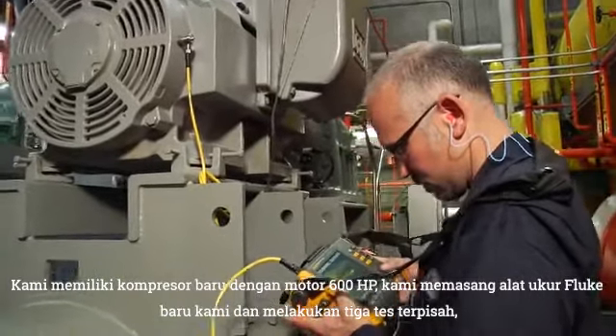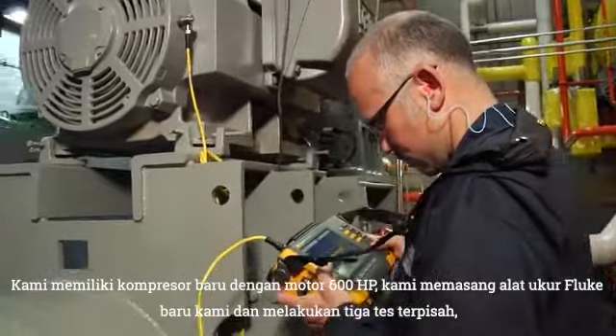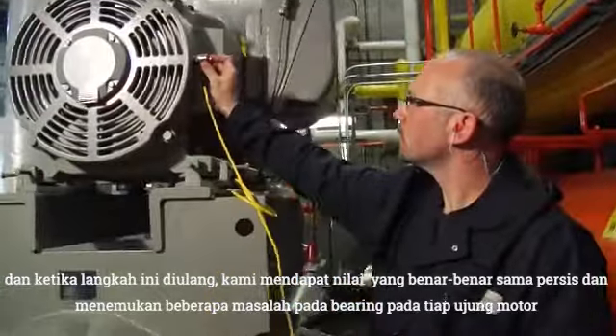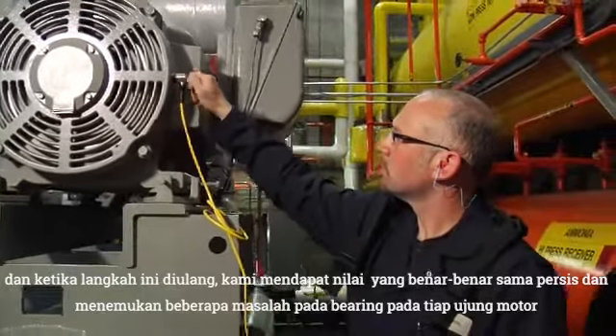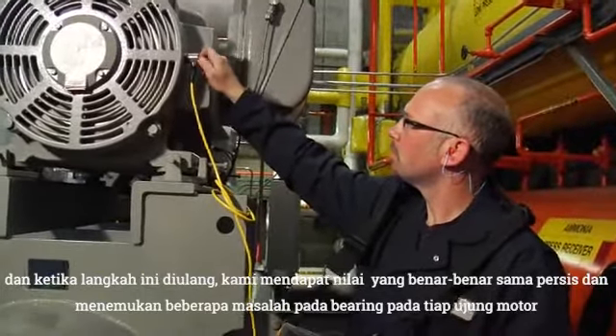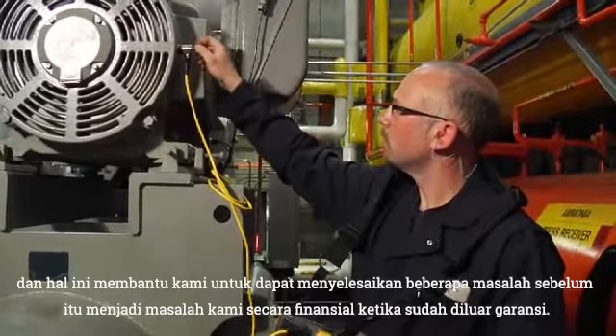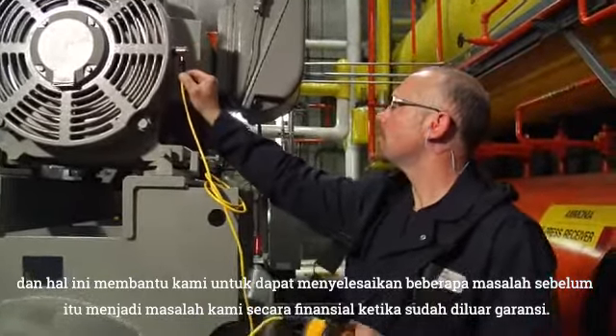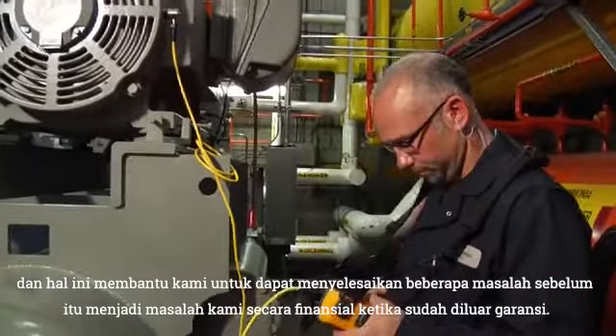We hooked up our new Fluke meter and did three separate tests, and they all repeated exactly the same, and did actually find some slight motor bearing end wear on each end. That's actually helping us so we can get some of these problems taken care of before things like that become out of warranty and become our problem financially.